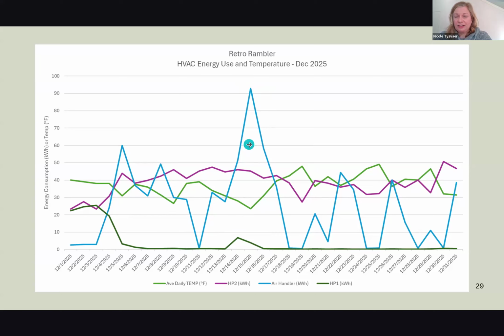A couple of interesting things — I'm glad we did this analysis. One, we learned the electric resistance backup heat was turning on when it shouldn't, and it caused huge spikes. This one day we had over 90 kilowatt hours, this spike right here. And two, obviously it's not communicating well with the thermostat, because we really didn't want to be freezing on these different days.